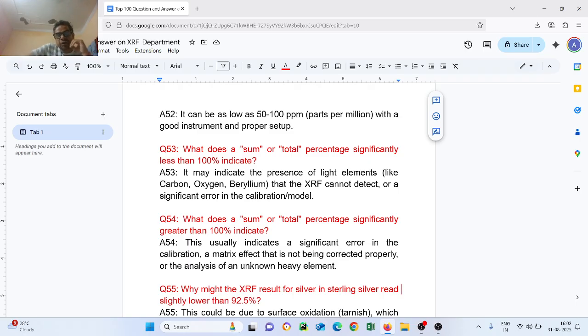What does a sum or total percentage significantly greater than 100% indicate? This usually indicates a significant error in the calibration, a matrix effect that is not being corrected properly, or analysis of unknown heavy elements.